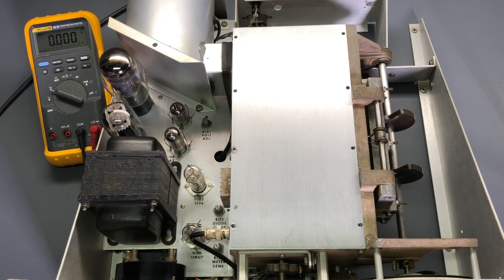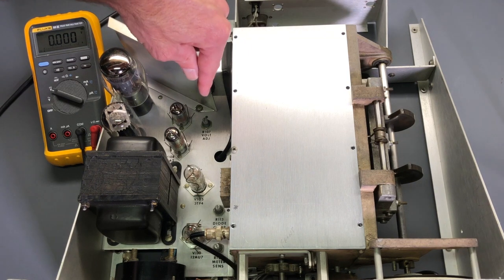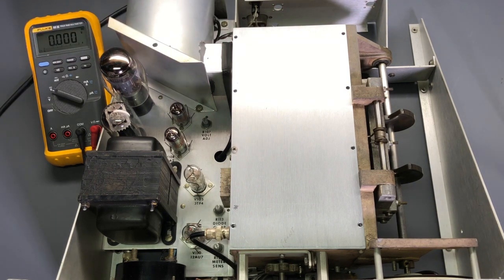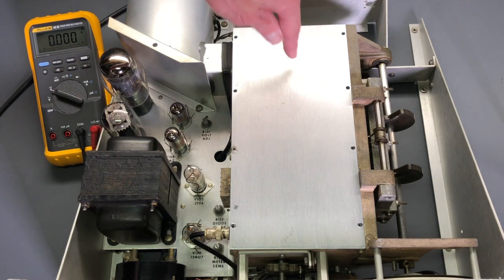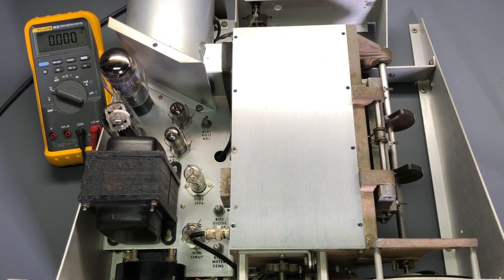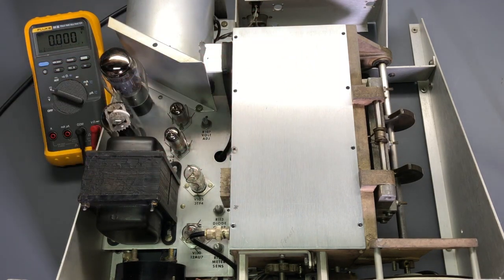So the final thing that we need to do is take one last reading on the B+ voltage just to make sure that it remains okay. Again, it's that regulated B+, and you can see down here R107, the voltage adjustment. We can adjust that if needed. So that convenient test point is the plate of the output tube under this cover. During all of the testing, particularly when the amplifier was under load, I had this cover in position with just the one screw holding it in, securely in place.